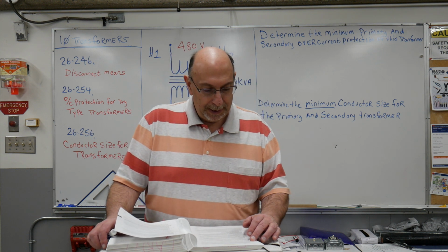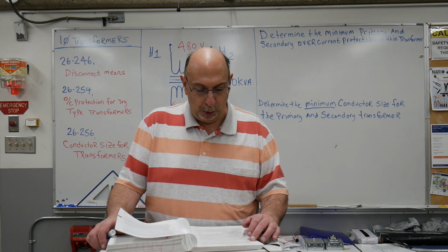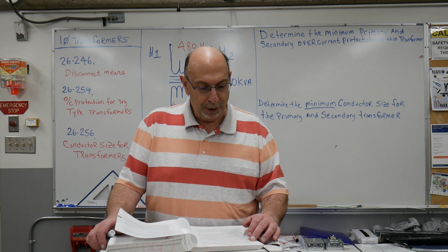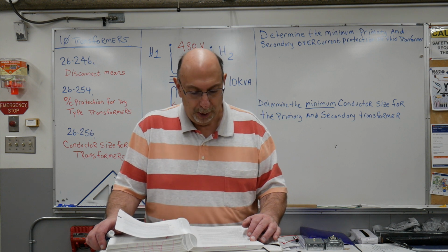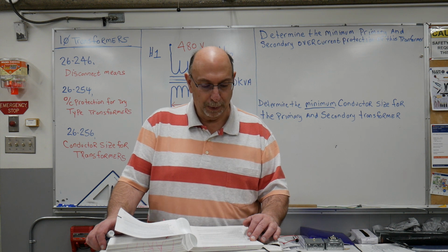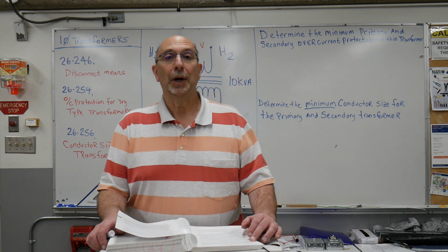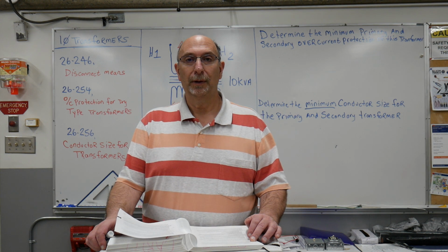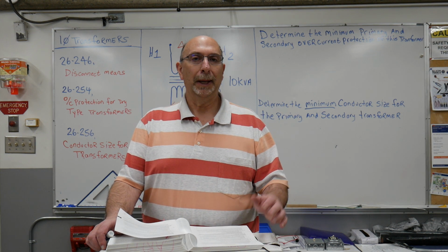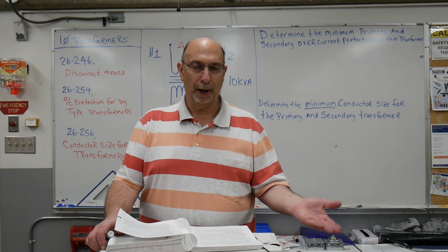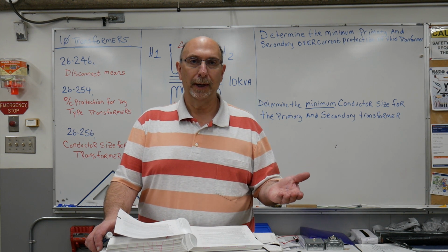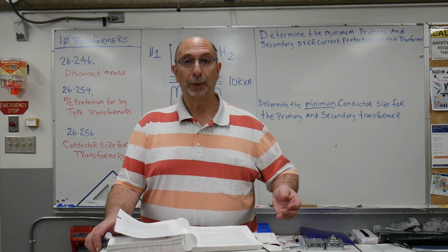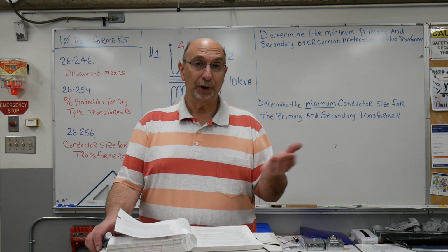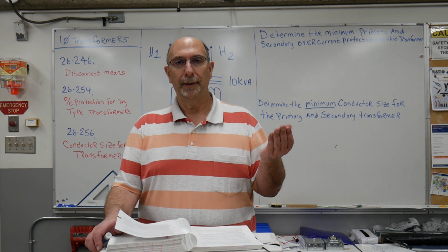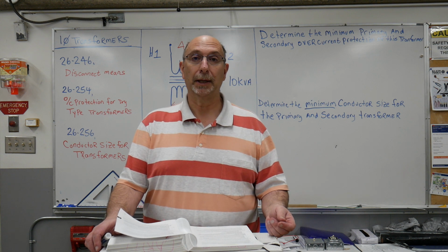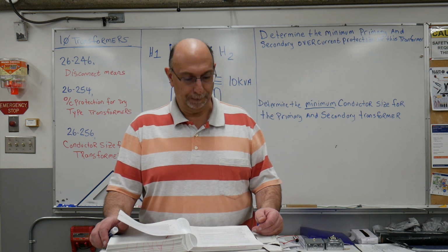Subrule 3, conductors and cables used for connection to air-cooled, dry-type transformers shall be permitted to enter a transformer enclosure through the top only when the transformer is marked to permit such entry. I've never seen a transformer marked for approval for top entry. You normally want to come in on the lower half of a transformer, on the sides. That's to do with the problems of heat. Transformers generate a lot of heat. Heat rises, and if you have your conductors at the top, the heat has a detrimental effect. So you technically have to derate those conductors.